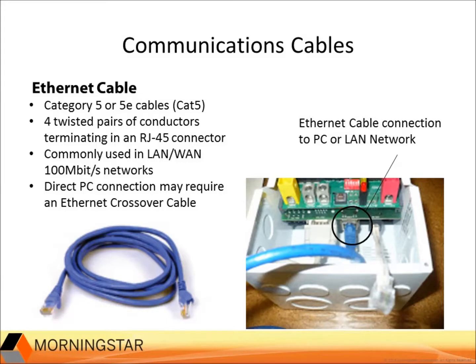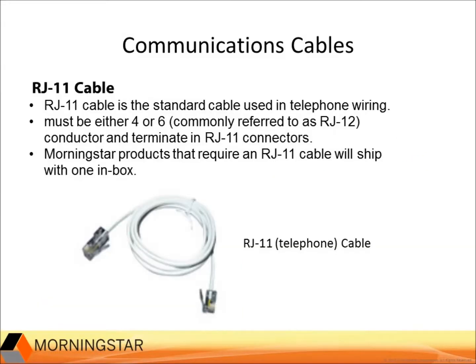Of course, you will need to wire it through one of the knockouts to get the cover on. To the left is an RS-232 cable connection, and left of the RS-232 port is where the EIA-485 connection is made. To the right side of the Ethernet is an RJ11 meter cable for connecting a TriStar meter. The Meterbus uses a plain RJ11 cable which is a standard telephone cable in the US and other regions. Six-wire cable will provide a better connection for longer distances.